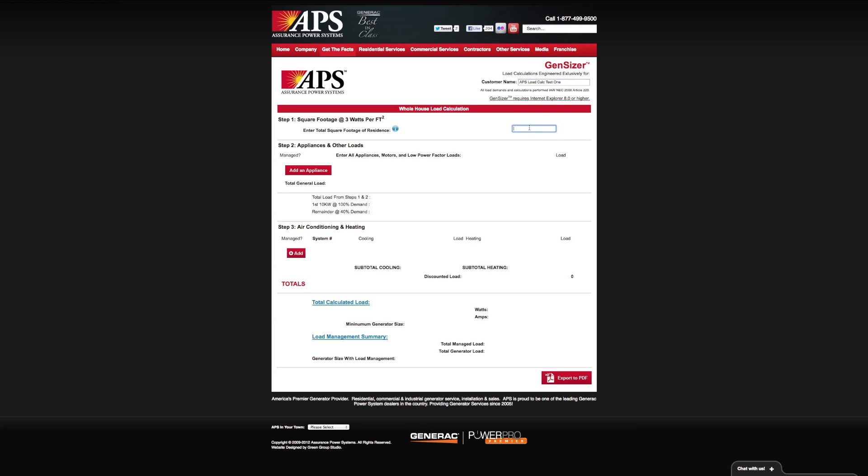Step one here is to do the square footage of your home. Depending on the building department, they may actually look at the property record, so you want to be as accurate as possible in this area. Let's assume we have a 3,500 square foot house. As you can see, as soon as you start typing, it's applying a formula, and that's three watts per square foot. That is based on the National Electrical Code requirement.